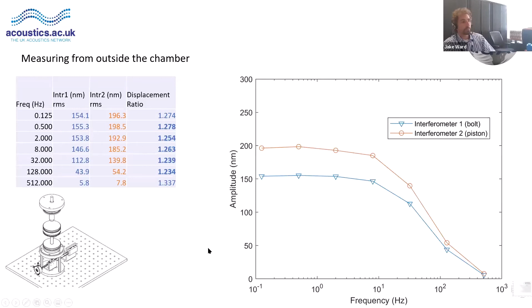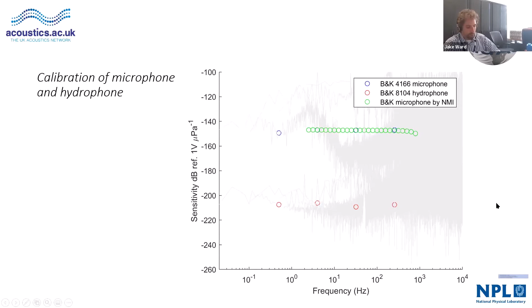And so I can compare them, as I showed you, the microphone and the hydrophone in the same chamber. We can compare the voltages between those, and we can take the results from another national metrology institute in Denmark, and we're interested in moving down in frequency to below 1 hertz here. And so this compares a microphone sensitivity to a hydrophone sensitivity, and that's where we're going with Infra AUV, which is a 3-year project.